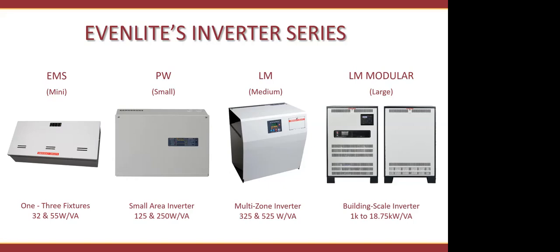And what that means is essentially you are taking every single emergency fixture in a building or a floor of a building, and you are allowing all of those fixtures to be powered by one single point, which eases the testing. It centralizes the testing for you. It's automatic fire code compliance. You don't have to mess around with battery packs, swapping out battery packs.